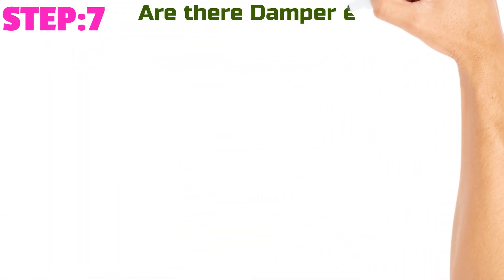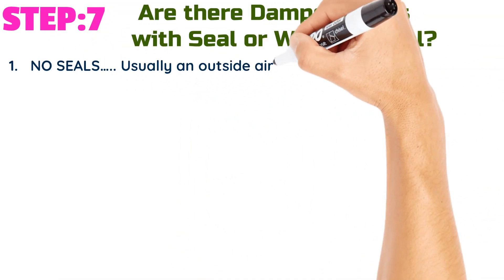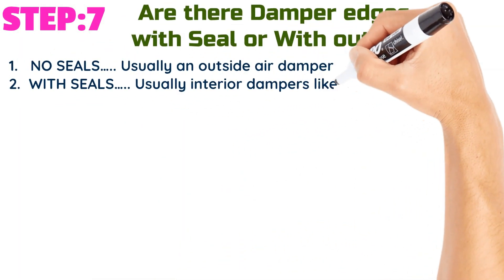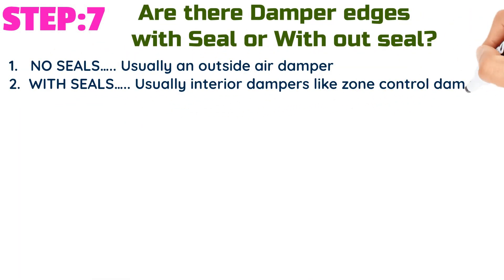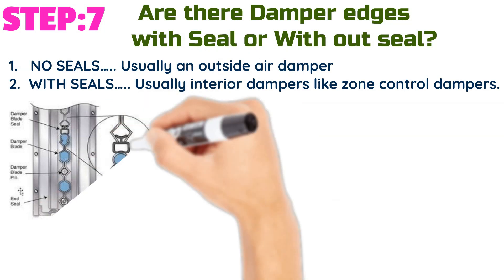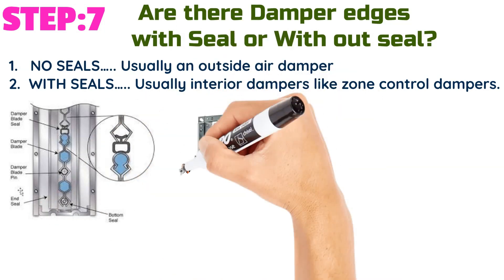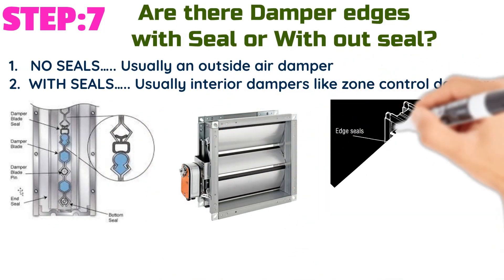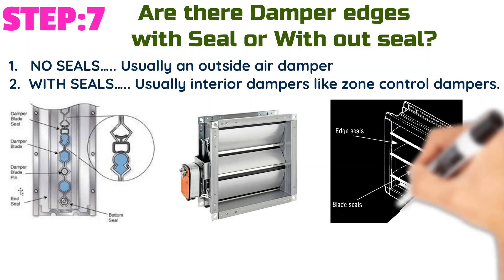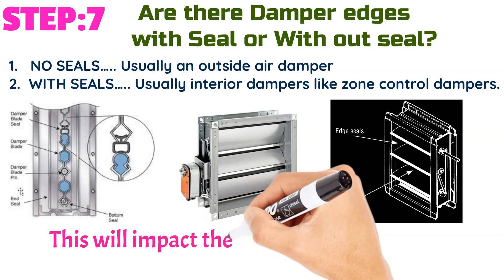Step number seven: Are the damper edges with seal or without seal? One — no seals dampers, usually an outside air damper. Two — with seals dampers, usually interior dampers like zone control dampers. This will impact the proper selection, as the seals add resistance, requiring more torque.